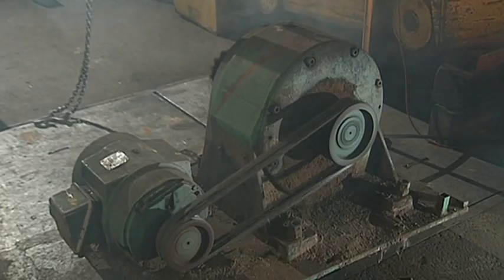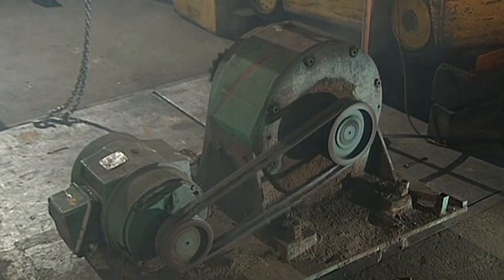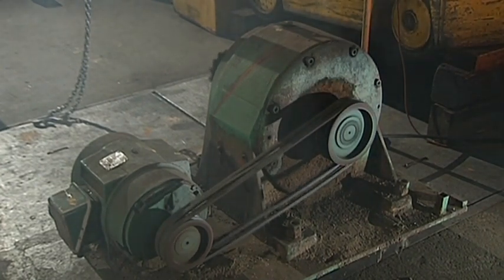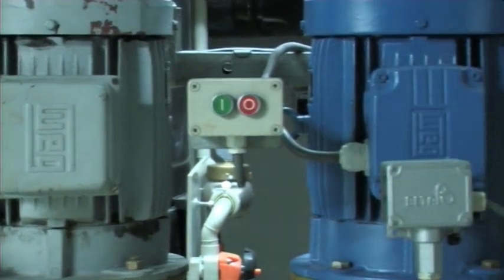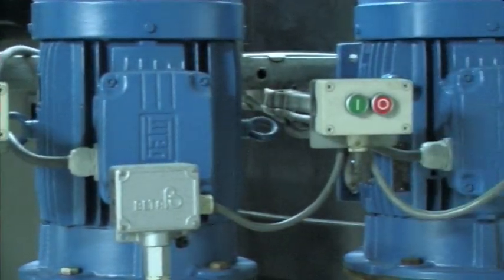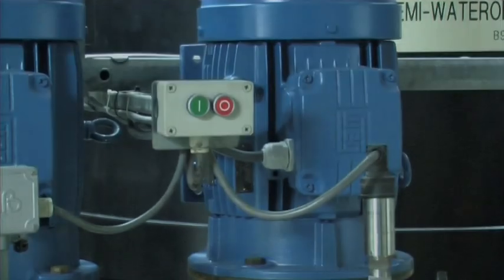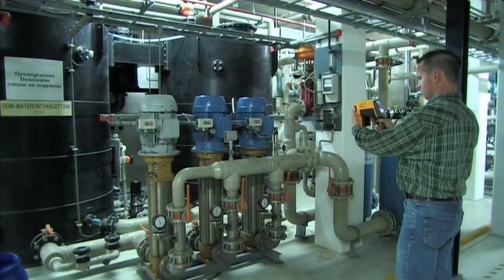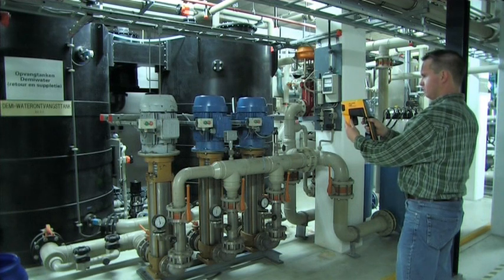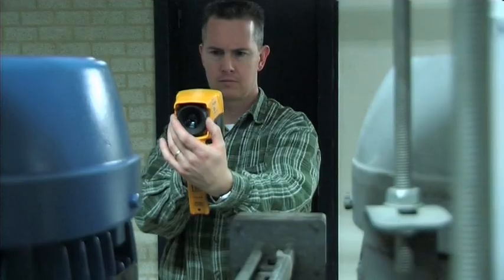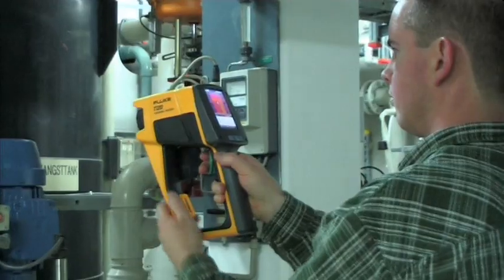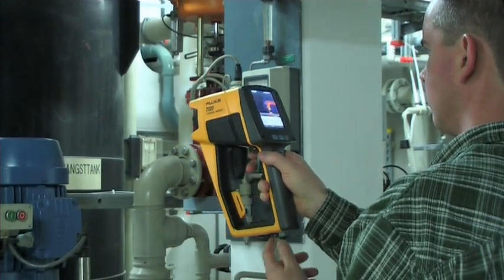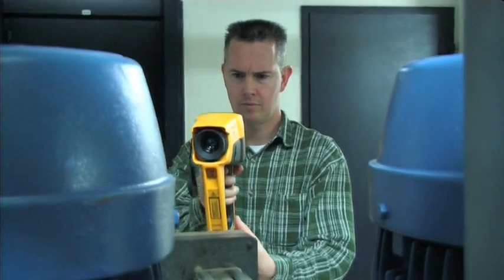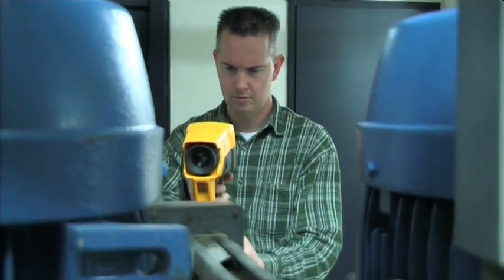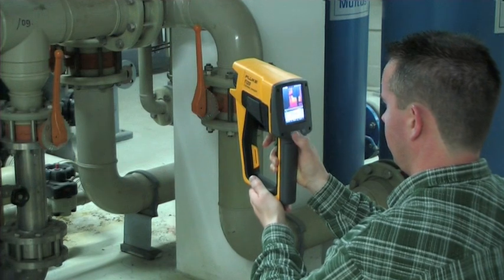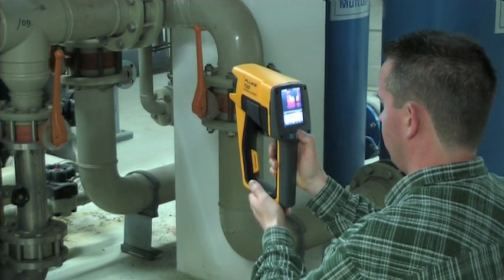If a motor runs at a temperature 10 degrees Celsius higher than specified, its life cycle is halved. This increases both maintenance costs and the risk of expensive downtime. A motor running at higher temperature than specified may be due to bad cooling, power quality related problems like harmonics or unbalance, or insulation problems with the motor windings. Mechanical problems such as bad alignment or broken ball bearings could also cause a motor to overheat.